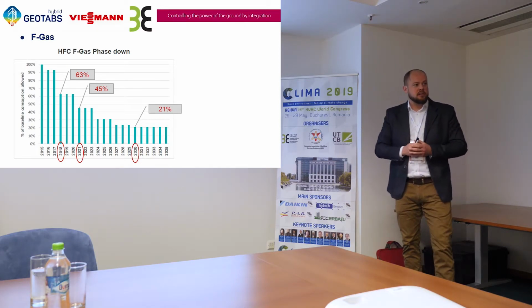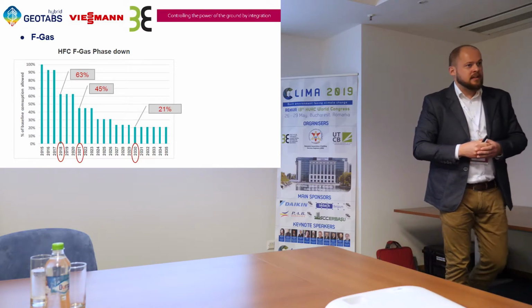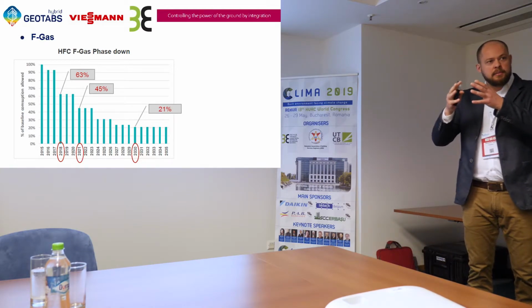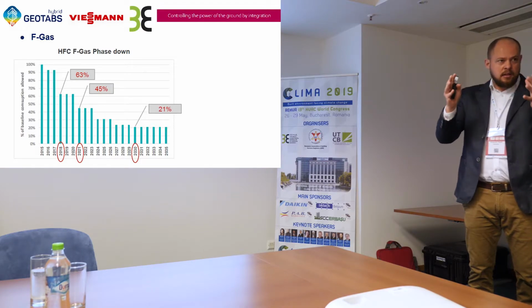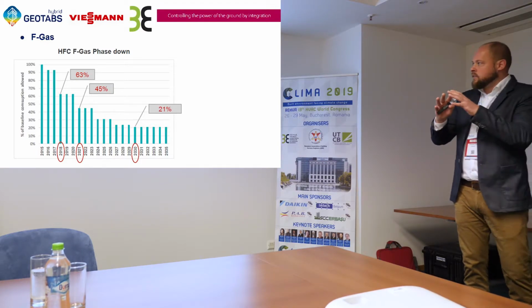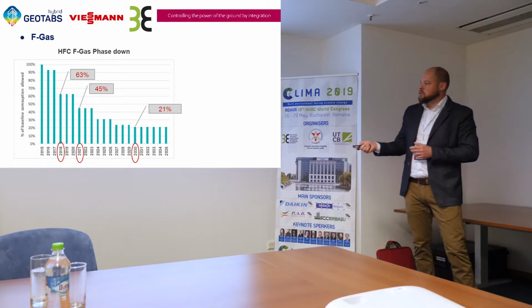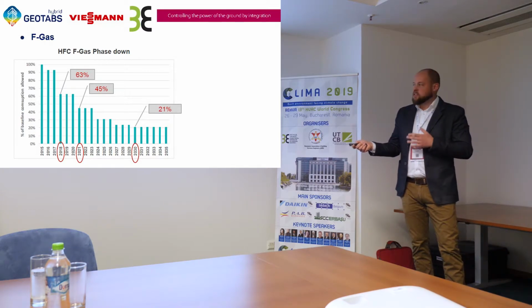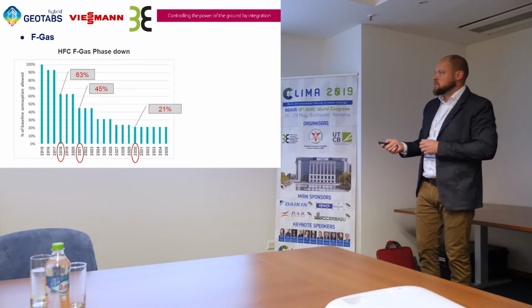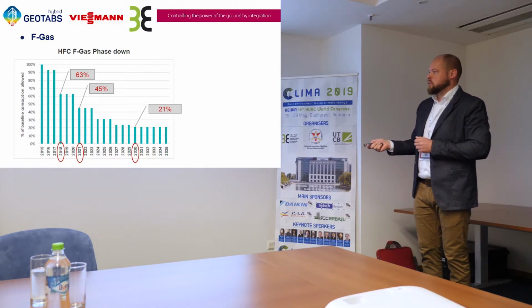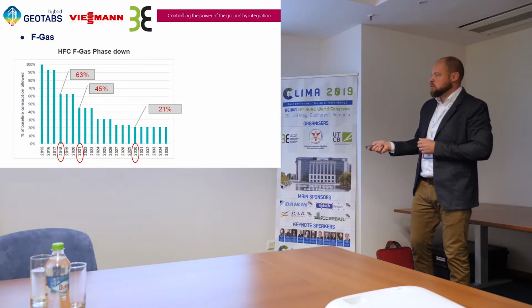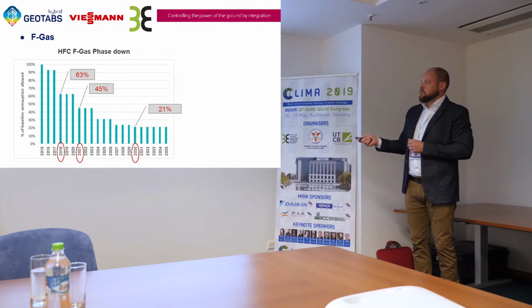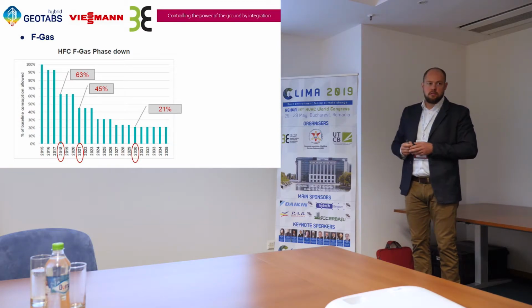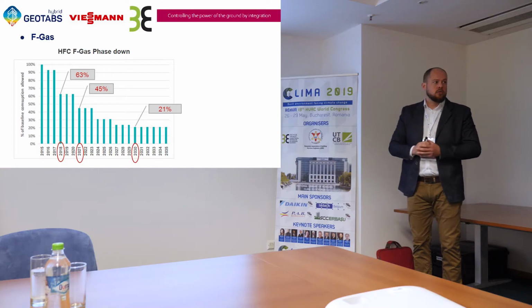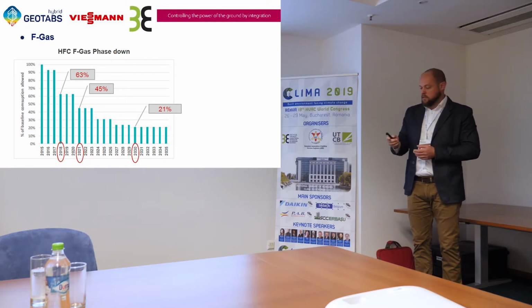And if you think logical, today we sell a lot of gas boilers and heat pumps are upcoming. So that means in the future we will have to be, with all the new heat pumps that are coming, we have to have a lower GWP than we had in total in 2015. So that's a challenge. We have to see how we can do that. If we see 2021, that's not so far away. It's only 45% of the original. And then in 2030, only 21% of the original is allowed. So we have to develop some new refrigerants to meet this demand.